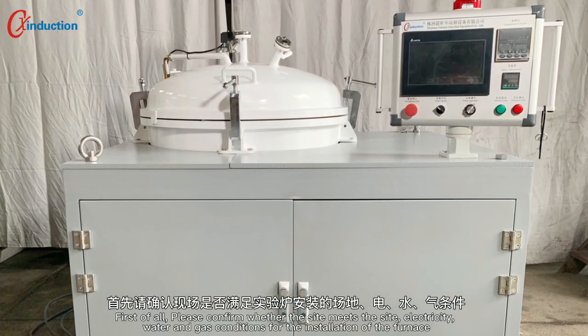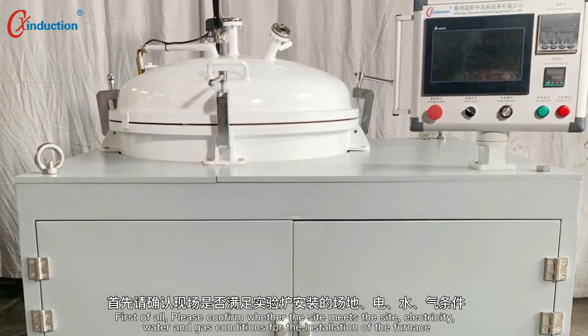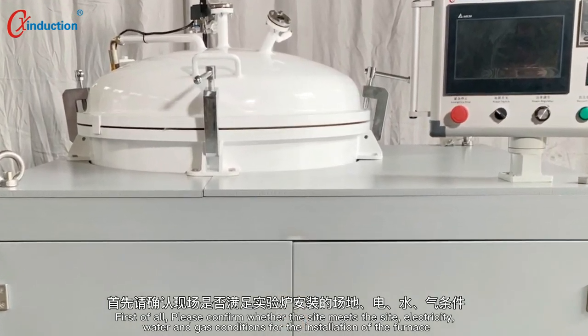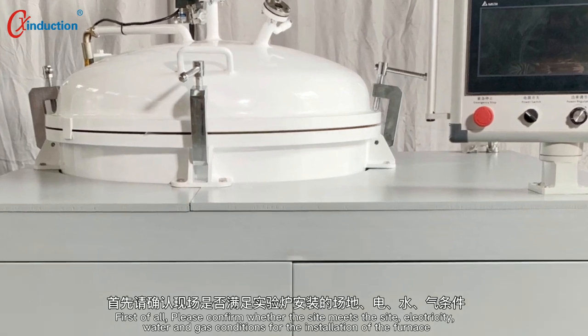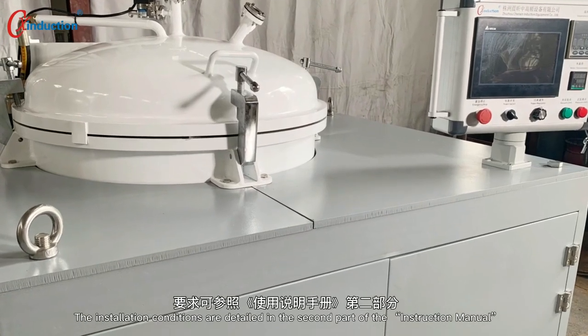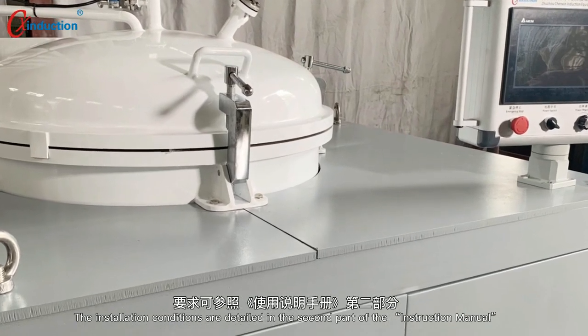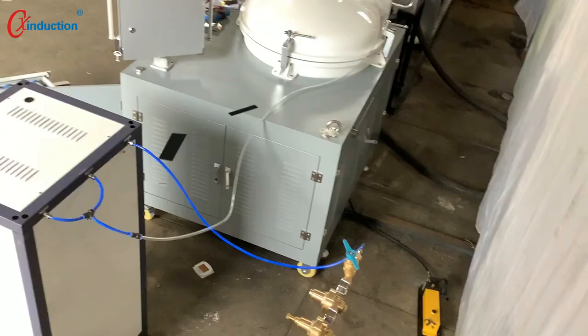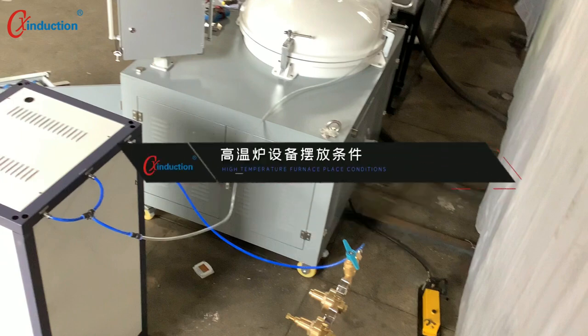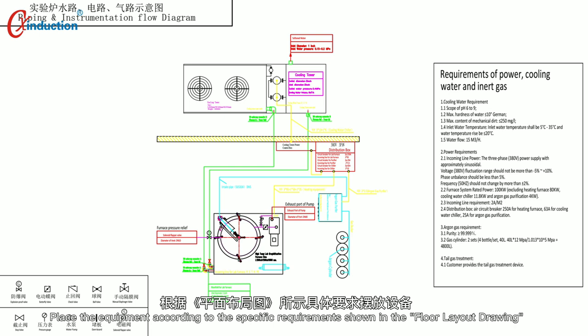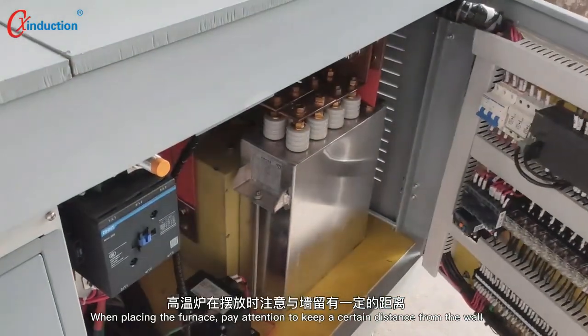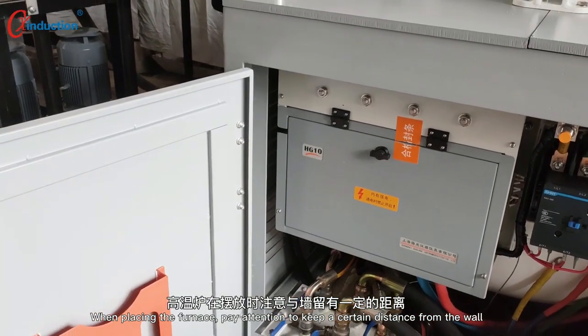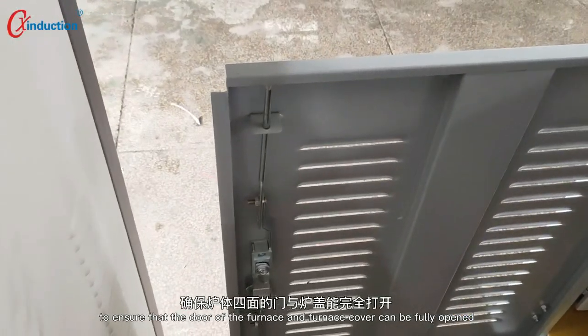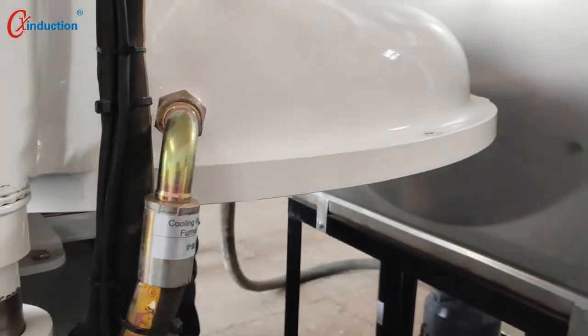First of all, please confirm whether the site meets the site, electricity, water and gas conditions for the installation of the furnace. The installation conditions are detailed in the second part of the instruction manual. Place the equipment according to the specific requirements shown in the floor layout drawing. When placing the furnace, pay attention to keep a certain distance from the wall to ensure that the door of the furnace and furnace cover can be fully opened.